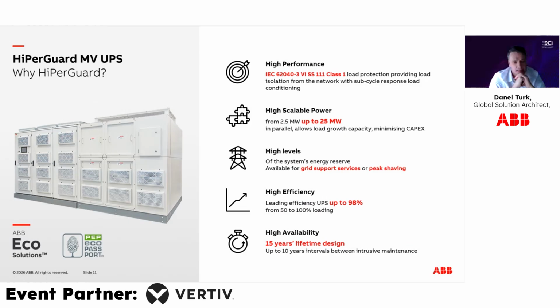It is scalable, coming in 2.5 megawatt blocks, and you can build it up with 10 blocks in parallel, giving you 25 megawatt blocks. Considering it's the same power you'd need in a low voltage UPS, there are significant benefits and savings, which I'll show on the next slide.